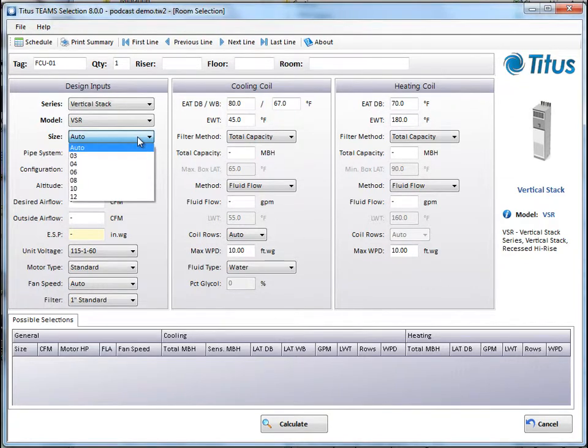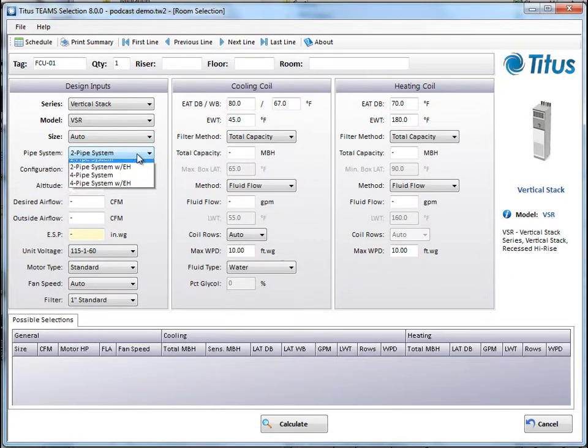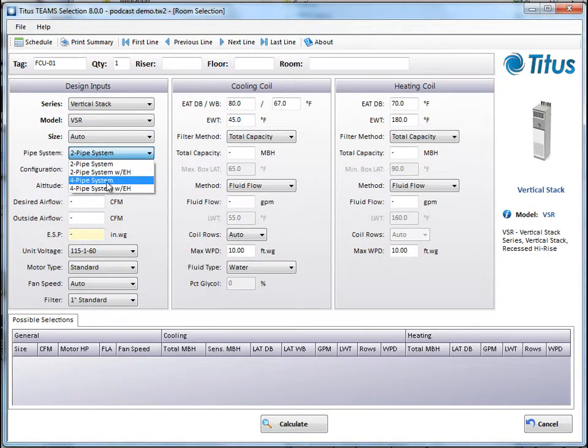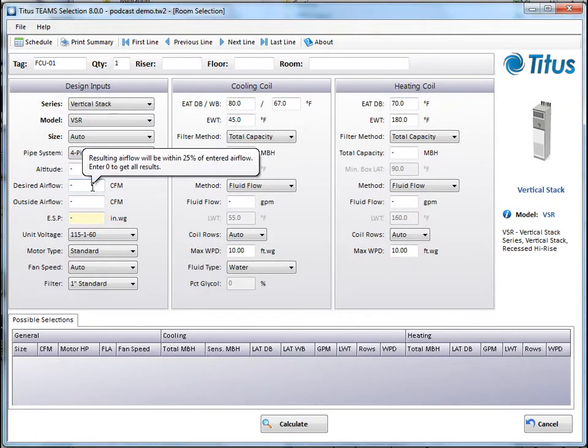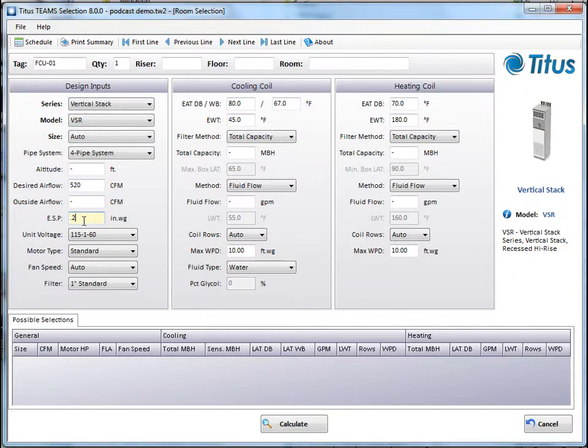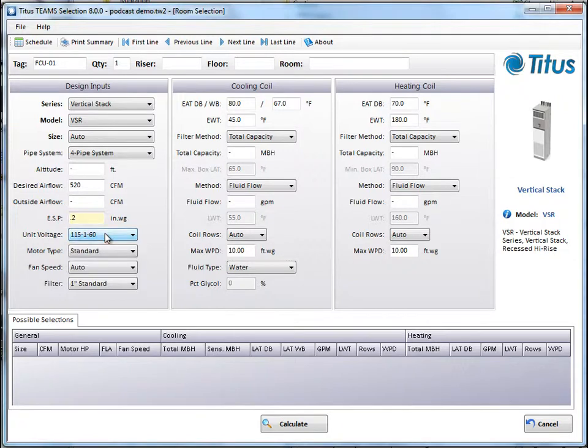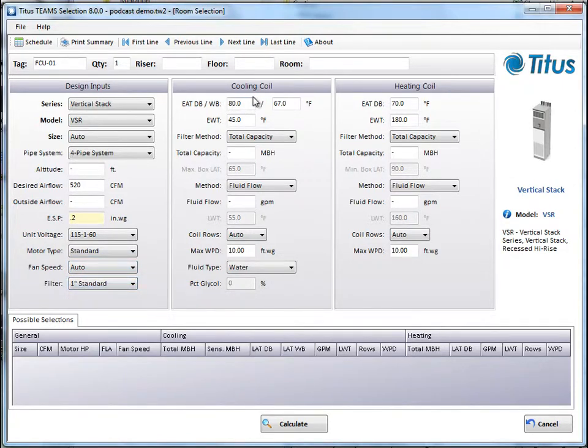Next, you can pick a size, or you can let it pick the size for you. I'll leave that on Auto. And now you can pick between a 2-pipe and a 4-pipe system. Let's go to a 4-pipe system. Now you input altitude and air flow and pressure information. I'm going to leave altitude where it is, but let's put in, let's call it 520 CFM. We'll do no outside air and 0.2 inches. I'm going to leave the voltage, but you can change your voltage here. I'm going to leave it as standard motor. Fan speed, I'll let it select for me, and then I'll leave it with just a 1-inch filter.